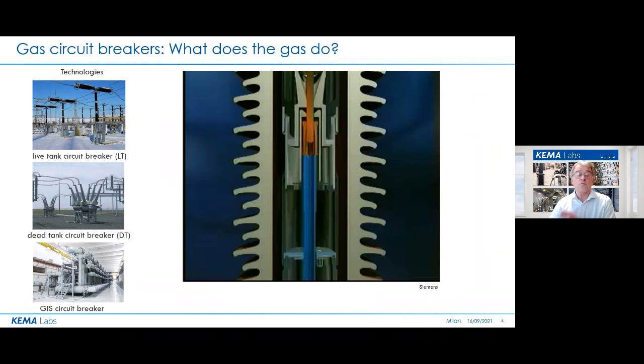So let's have a look at the importance of gas in a gas circuit breaker. We see 3 different technologies of gas circuit breakers: live tank breakers, dead tank breakers, and GIS circuit breakers. This is not only for gas breakers, but also vacuum breakers have an outside appearance which is similar to that. We can have a look at the key part of these circuit breakers, the arcing chamber. Gas breakers all look similar to this. First of all, they are of course filled with gas. Gas is one of the important features of the device.